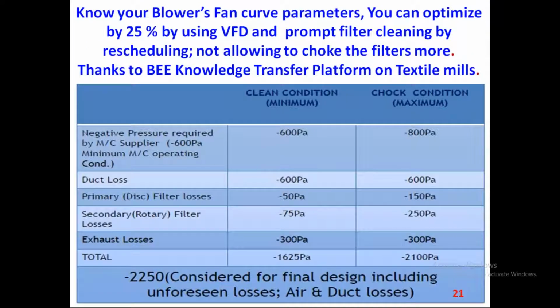I'll just show you, thanks to this BEE knowledge transfer platform, in the textile mills, some big textile group has shared this one case study. Normally we find the negative pressure required by the machine supplier says 600 Pascal, whereas the duct loss here is 600 Pascals more. That is why we always say optimize your duct sizes, make the duct sizes smaller, and let us reduce all the bends and sharp bends to reduce the Pascal losses.